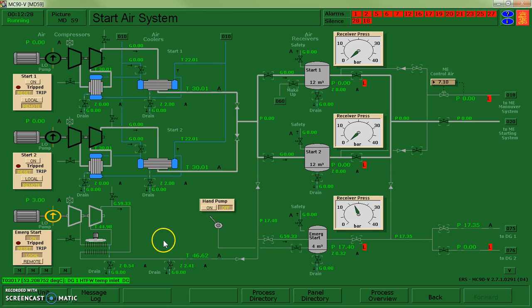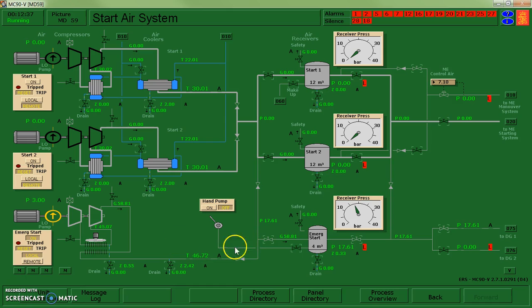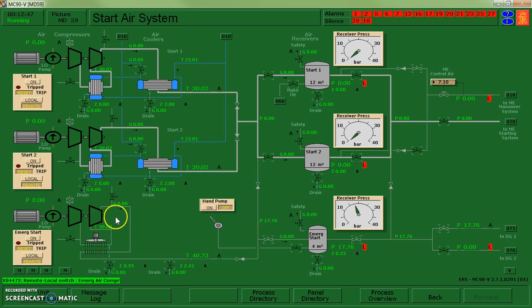I'm going to go to my start air system. Another alarm. Again, cooling water was not warm enough yet. So that'll go away once we warm up. Just so I don't forget, I'm going to want to make sure that I'm on top of this, either setting to automatic controls or else I don't overfill this tank. I'm just going to turn off this guy for now. Eventually what I'm going to do is switch him over to remote and set him into automatic.